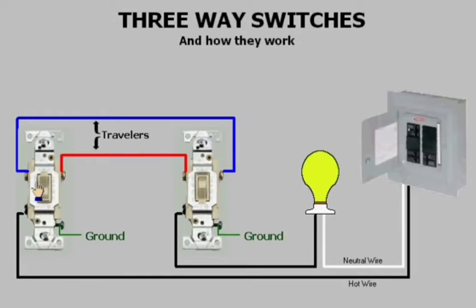When a person switches one of the three-way switches, the light comes on. When they switch the other, the light goes off. If you look inside a three-way, you will see that it is a single pole, double throw switch. When you switch a three-way, it breaks with one contact and makes with the other.